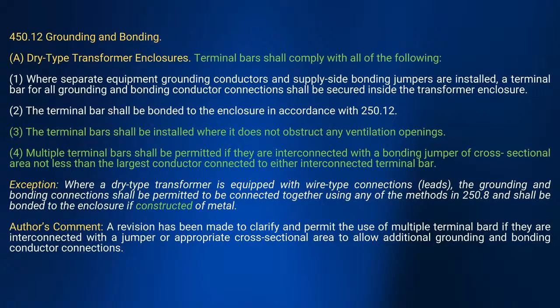Then they made a little change here—basically a revision to help clarify and permit the use of multiple terminal bars, if they're interconnected with a jumper, or you're looking at the appropriate cross-sectional area that allows for this additional bonding and grounding conductor connections.